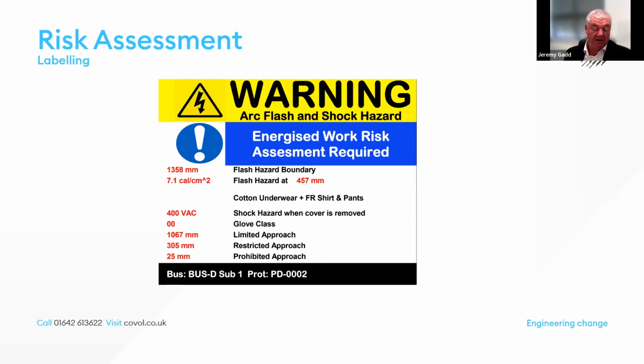Well, that FR is now known as AR. FR was fire rated. That text has now been changed to AR, which now denotes arc rated. But these are typically the labels that you would see on switchgear following an arc flash hazard assessment. And this gives the guidance that's required, along with the typical PPE requirements, distances, and the incident energy levels.